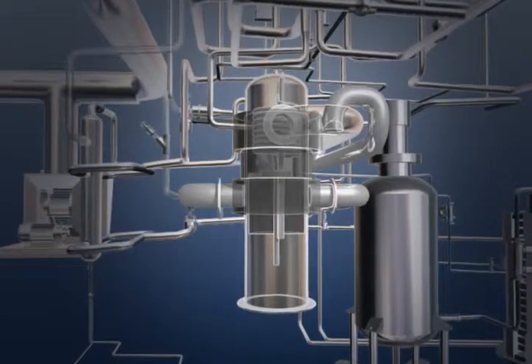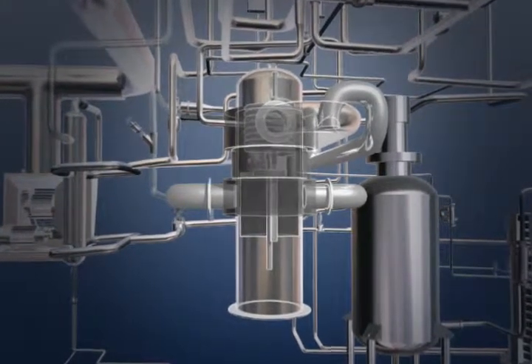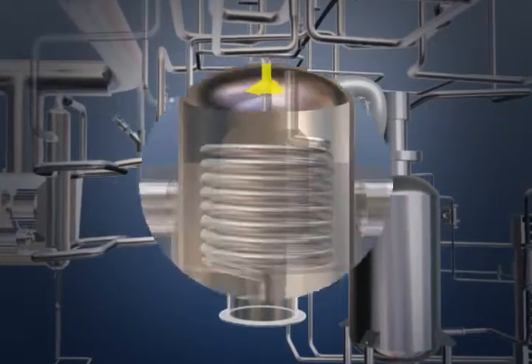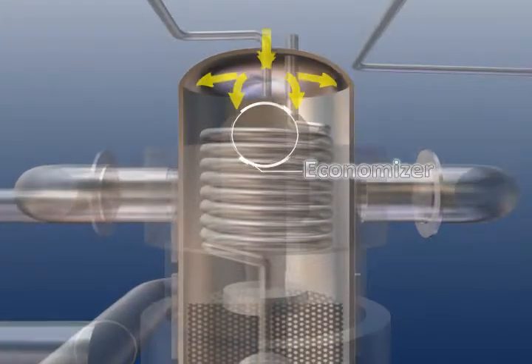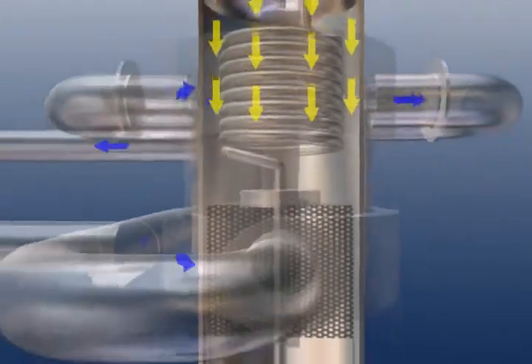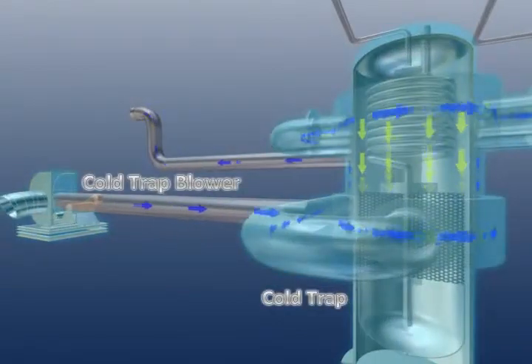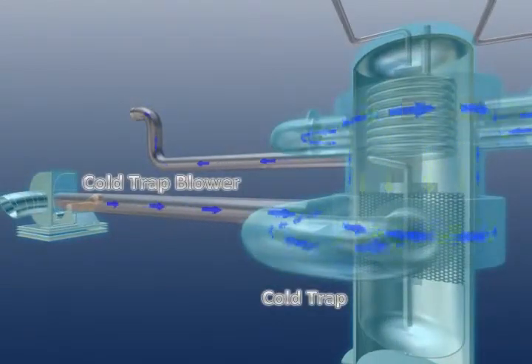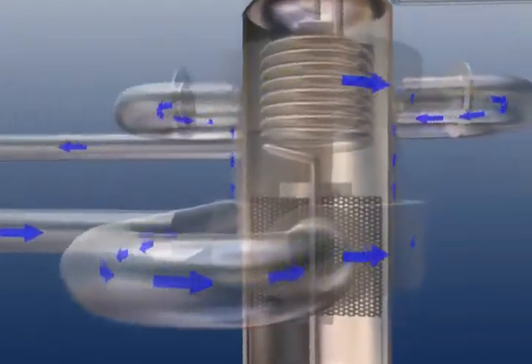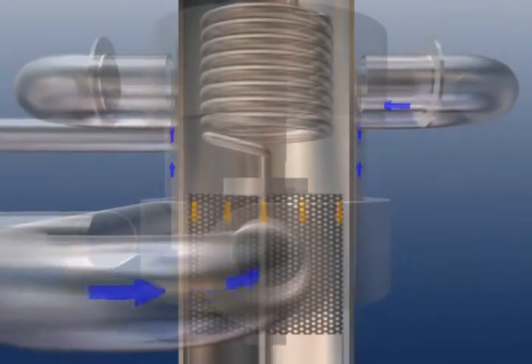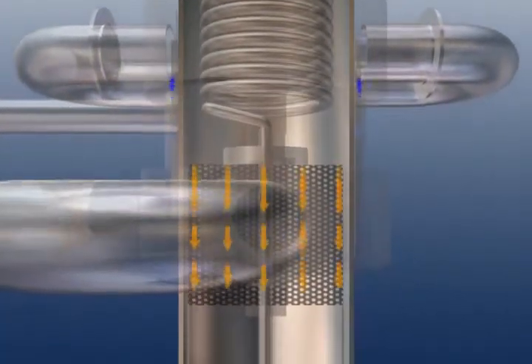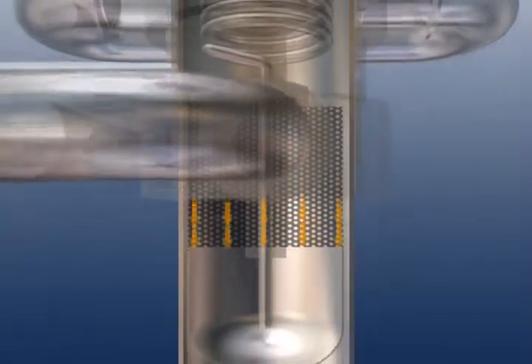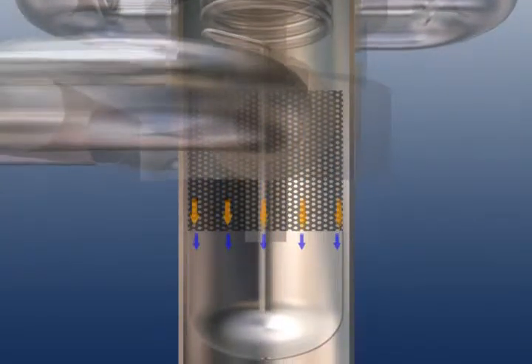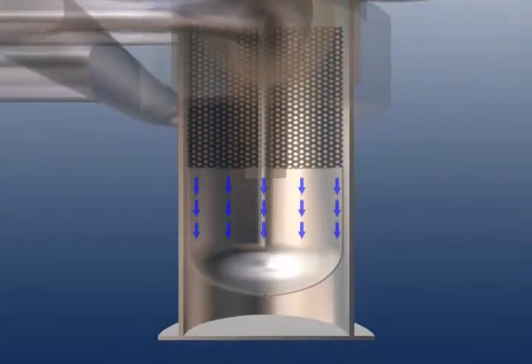The cold trap provides the function of sodium purification by removing the impurities in liquid sodium. The cold trap is composed of a trap, a mesh packing, a heater, and a cooling blower. The impurities in liquid sodium can be removed by capturing them at the mesh packing in the cold trap after the temperature falls below their solubility. Finally, the purified sodium returns to the main sodium loop.